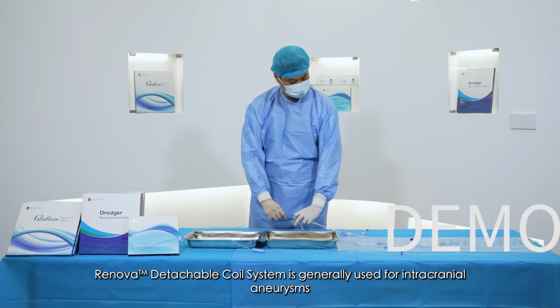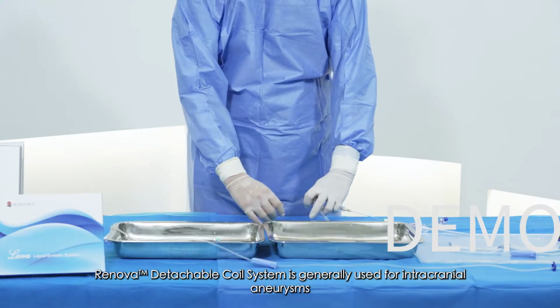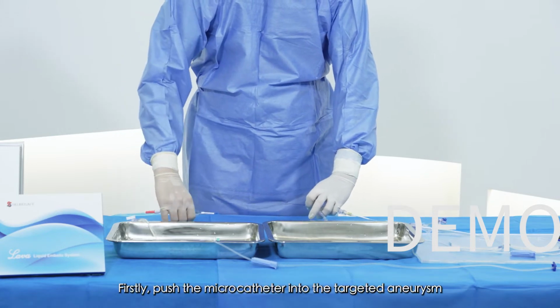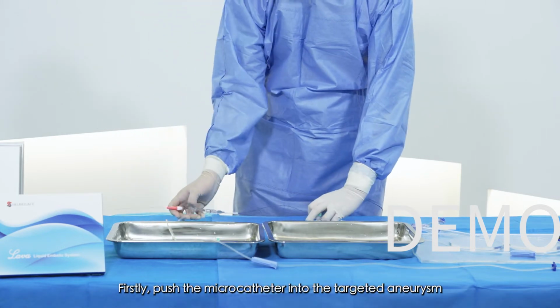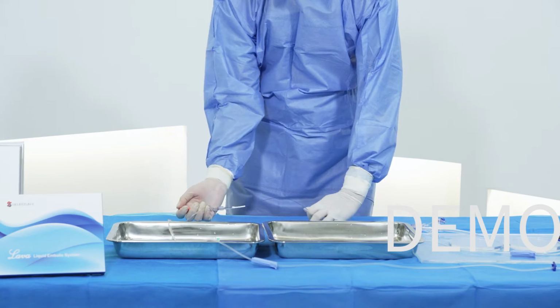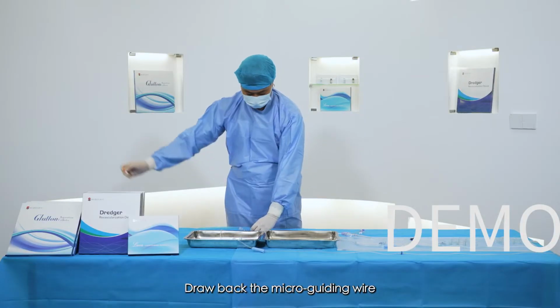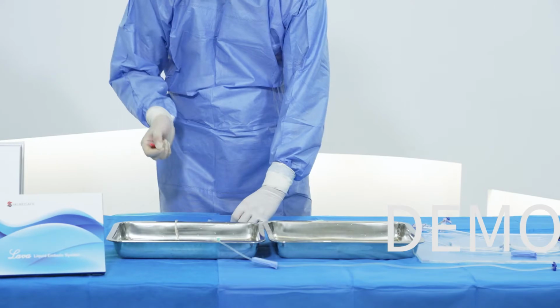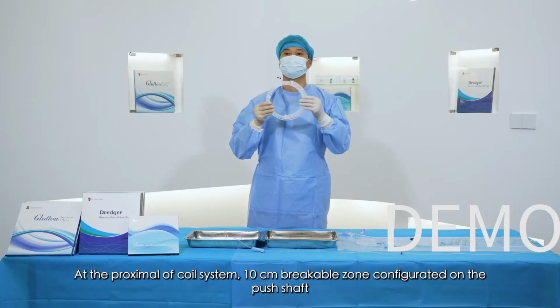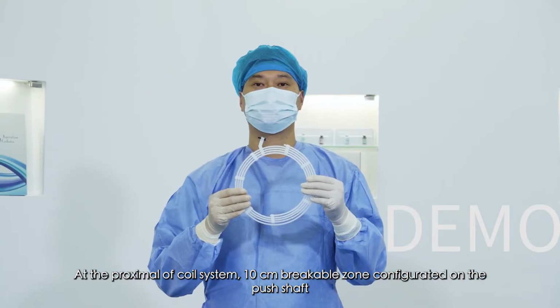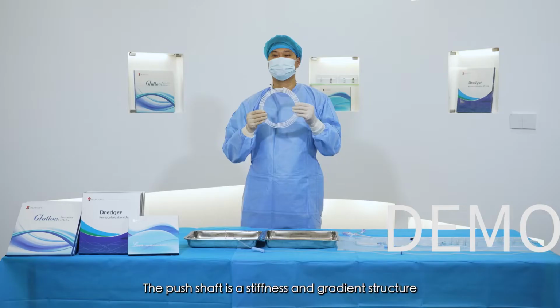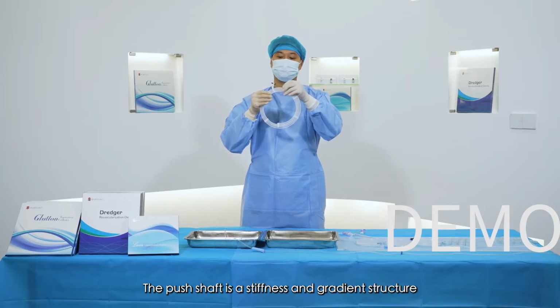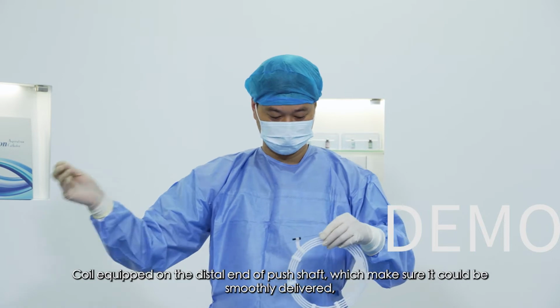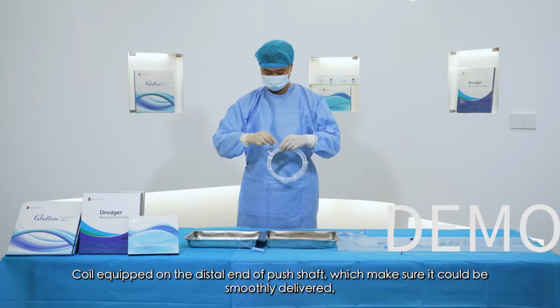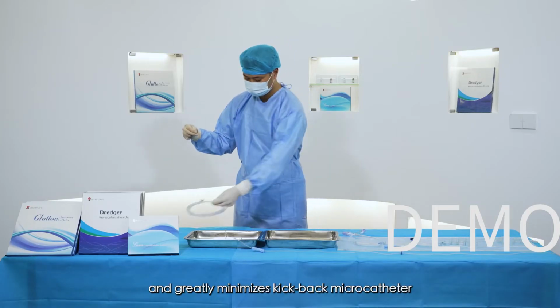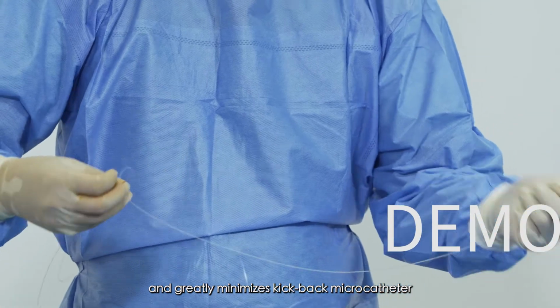Renova Detachable Coil Systems are generally used for intracranial aneurysms. Firstly, push the microcatheter into the targeted aneurysm. Draw back the micro-guiding wire. At the proximal end of the coil system, a 10 cm breakable zone is configured to push the shaft. The push shaft is a stiffness and gradient structure, with the coil equipped on the distal end of the push shaft, which makes sure it can be smoothly delivered and greatly minimizes kickback of the microcatheter.